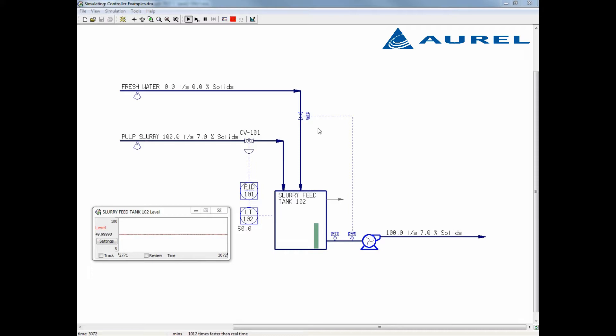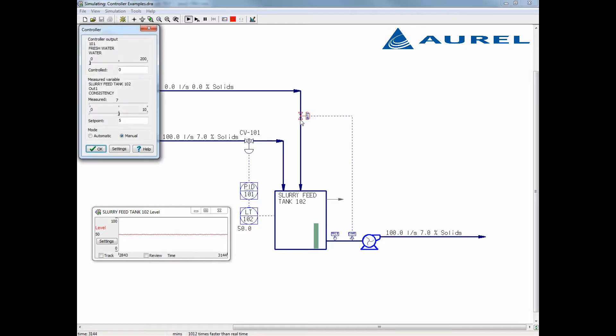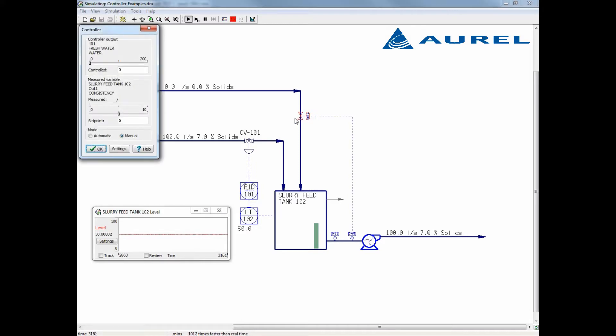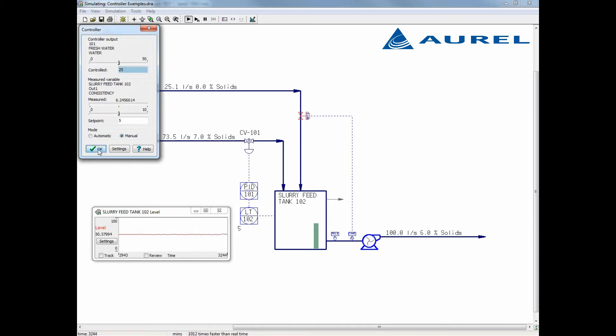Right now we can see that no fresh water is flowing in. To tune this, I will select the shortcut controller here. Notice it is under manual control. I will enter in some flow manually in order to get closer to our desired set point. This will improve the tuning parameters we find during the autotune, which we will do now.